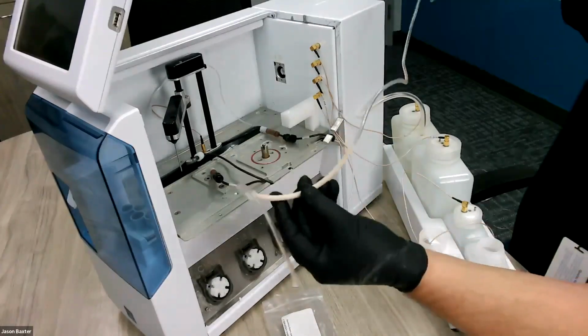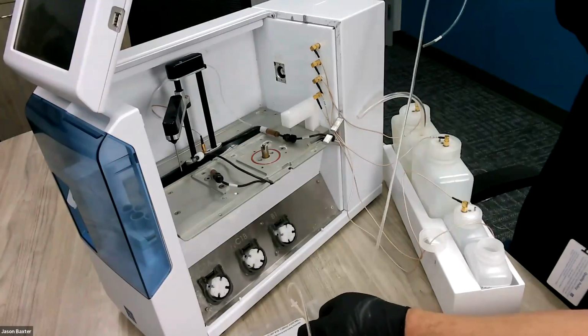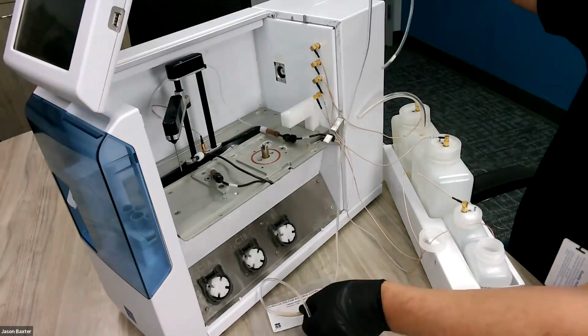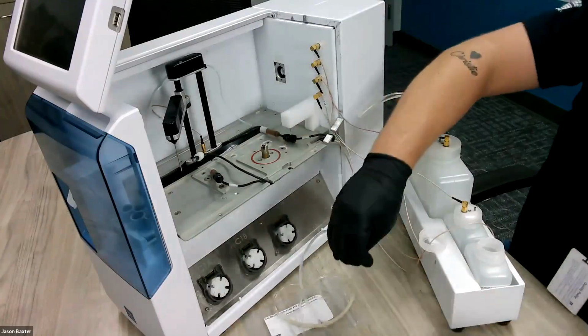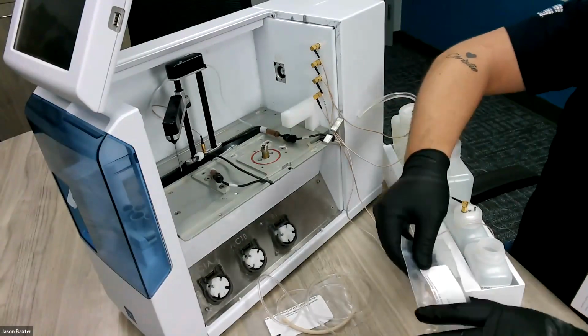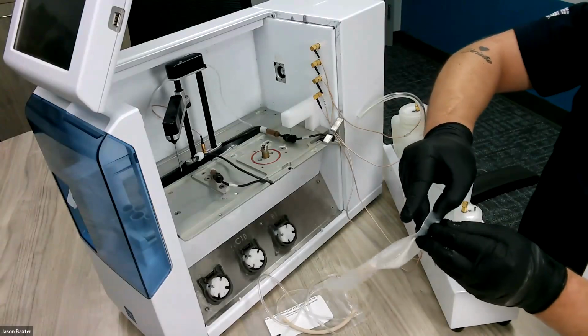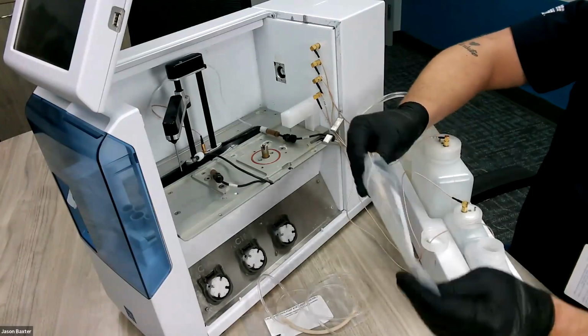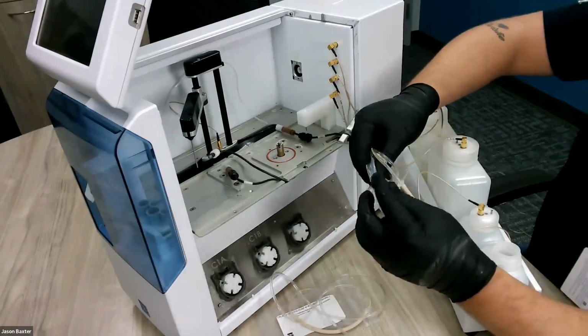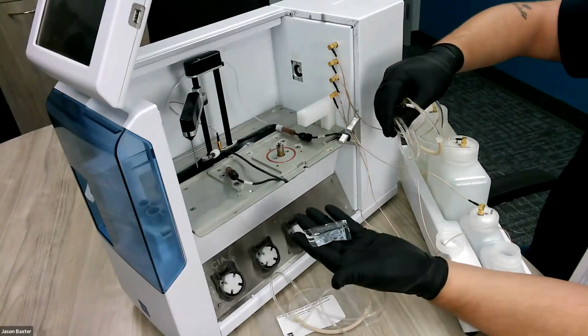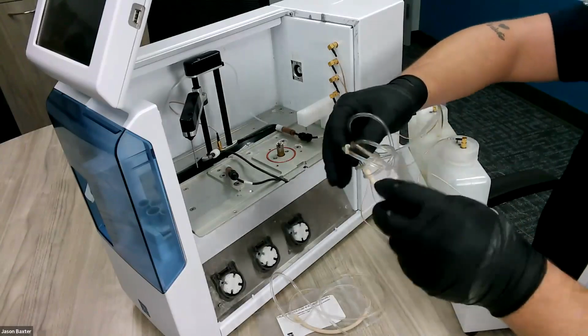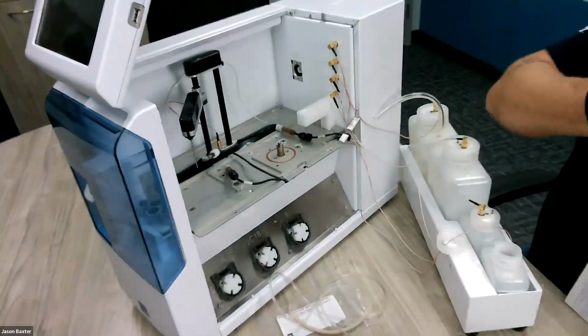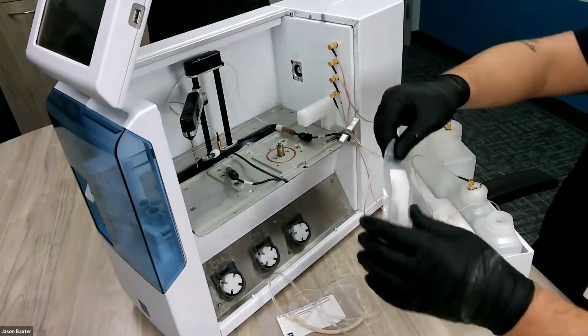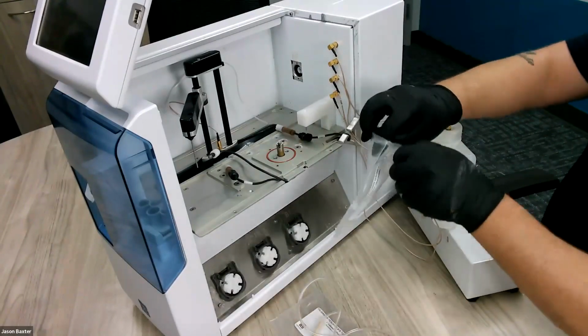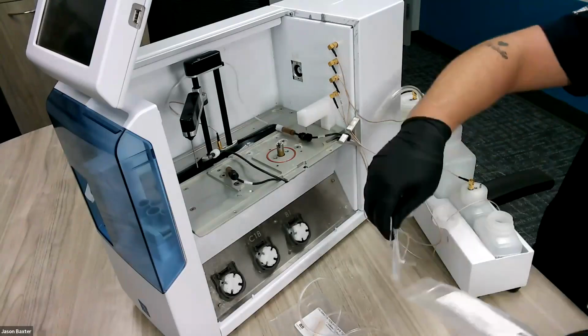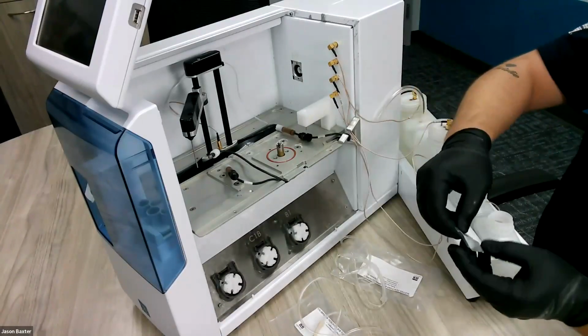So what I do is I take the tubing, I just opened up the bag for 1B. So I'll set the tubing on the bag for 1B immediately in front of pump 1B. Try to make my life a little easier here. I do the same. The next bag is calibrator 1A. You'll notice calibrator 1A has a small silicone grease packet inside. You're going to need that here in just a little bit. And lastly, the buffer pump. Again, with its own grease pack.